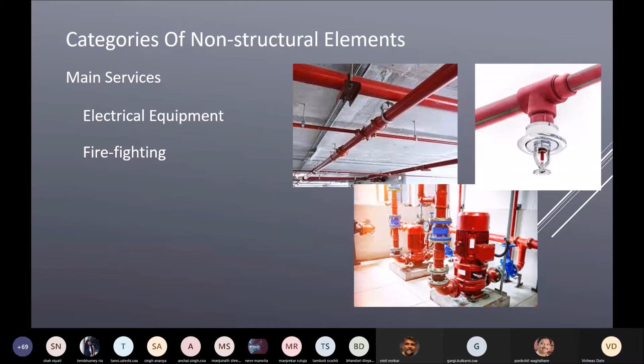Then of course the mechanical equipment. Typically your AC and everything will be shut off in the event of an earthquake, so that is not an issue. Your AC may not work, but when you want to occupy the building again, maybe a week or 10 days after the earthquake event, you should not be required to reinstitute all these systems from the word go. They should be more or less in working condition with minor repairs here and there, and they should be functional. That is the idea. So chillers, air cooled chillers, water cooled chillers, whichever they are, cooling towers, and your pumps that circulate the water in a water cooled system, all of those things. They all need their own protection in terms of what happens during an earthquake.